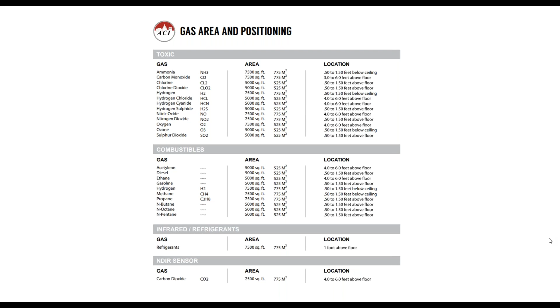We really recommend on bigger projects, not the home run 4 to 20, but the digital, because we can daisy chain anywhere from 32 digital sensors all the way up to 128, depending on the size of the job. The other thing we do, like I said earlier, is we'll take a look at your plans and lay it out for you. Normally, we'll have an answer back to you with a full layout in a couple hours, which isn't that bad time-wise.